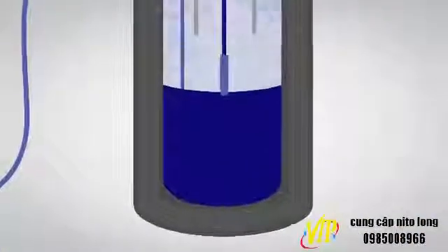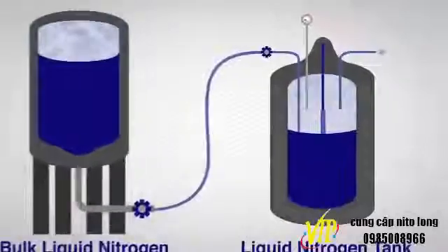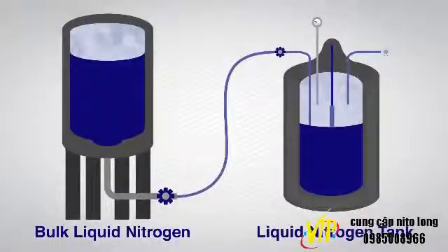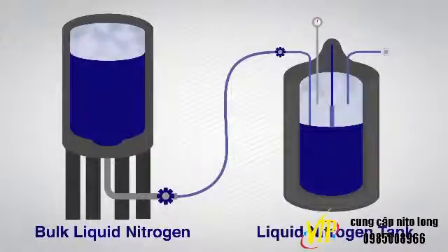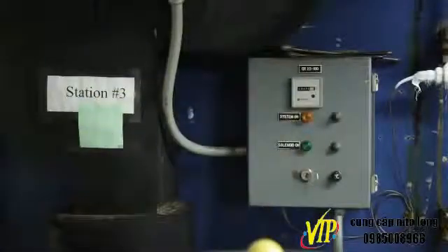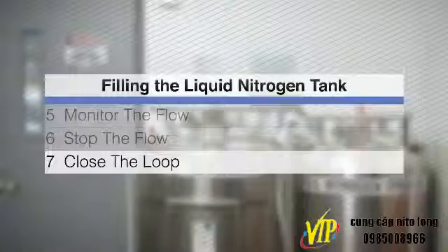The physical principle is that liquid will always flow from a vessel of higher pressure to a vessel of lower pressure. Before removing your tank from a fill station, don the proper personal protective equipment. Step 6, Stop the Flow: when the filling process is complete, flip the on-off switch to off. Step 7, Close the Loop: close the liquid valve, then the vent valve on your tank.